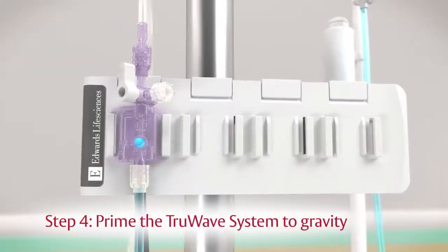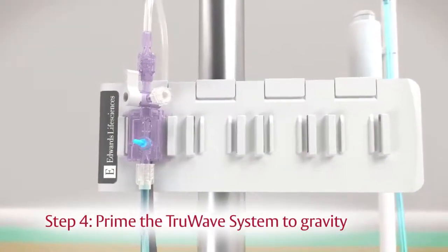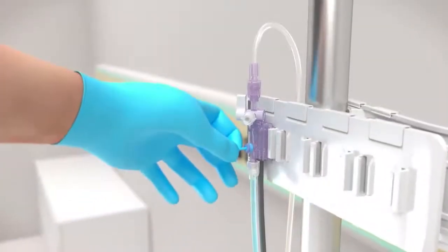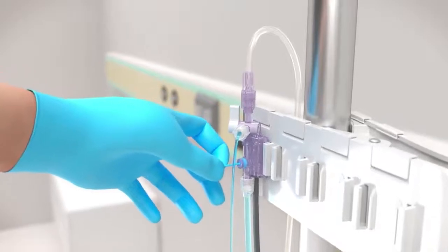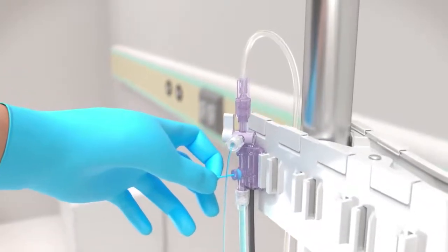Step 4: Prime the TruWave system to gravity to avoid micro-bubbles in the line. Pull the snap-tab flush device to deliver the flush solution through the TruWave transducer and out through the vent port's vented cap.